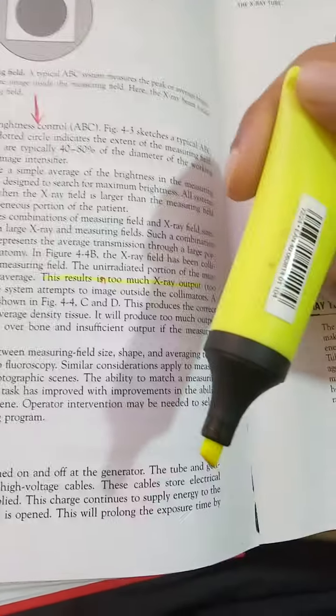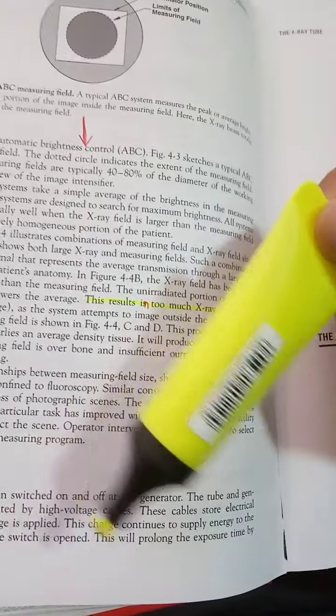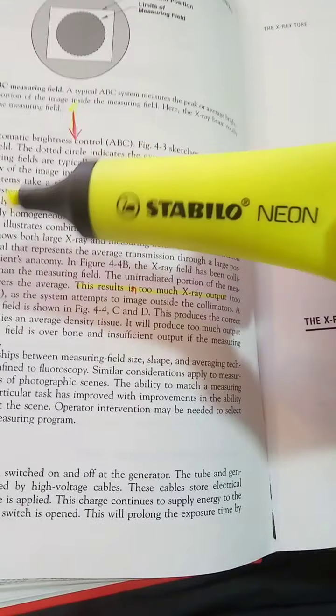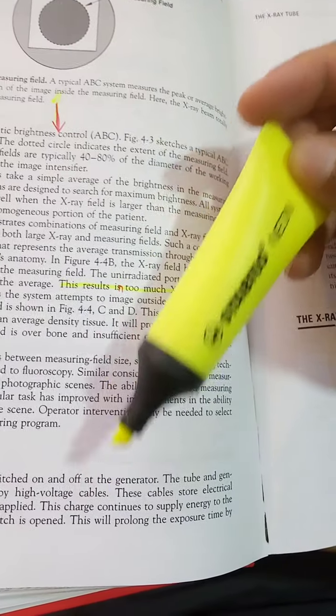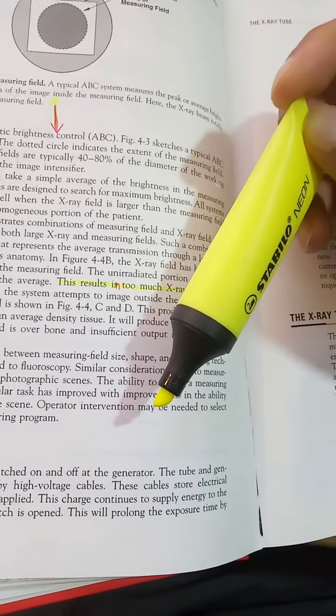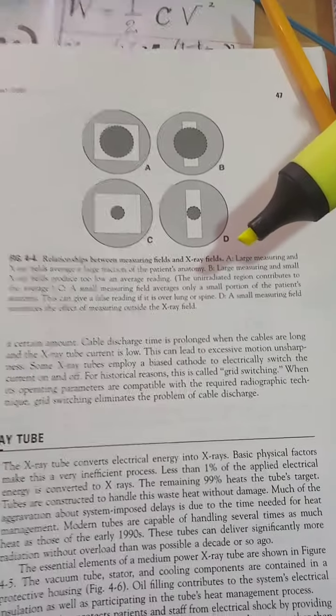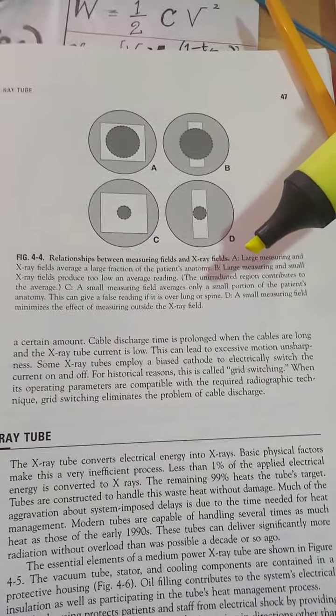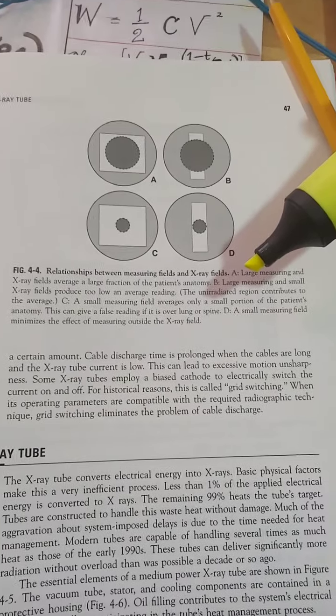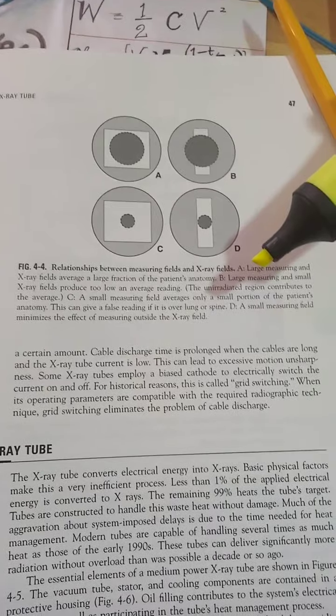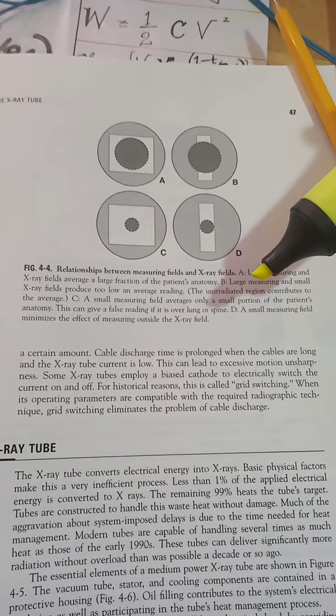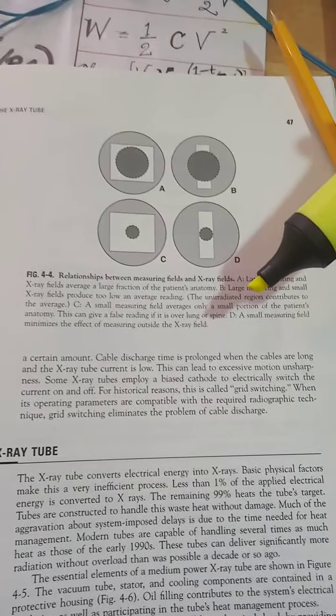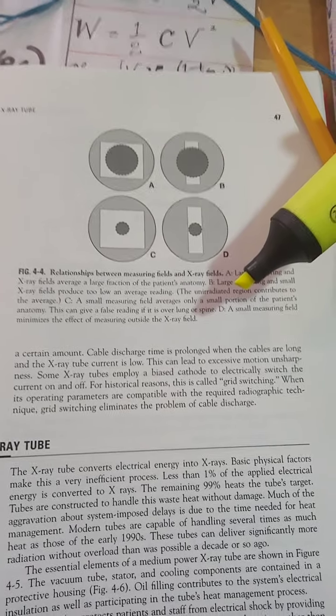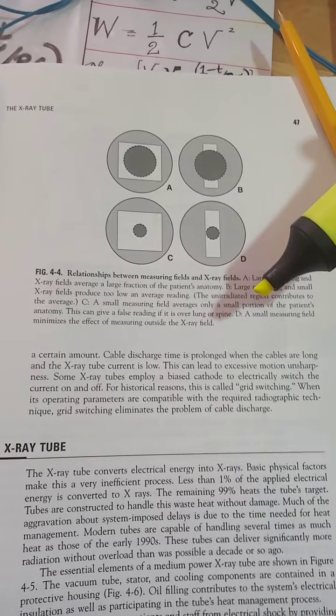The system is often switched on and off at a generator level, and the tube and the generator are connected by high voltage cables. These cables store electrical charge. When the voltage is applied, the charge continues to supply energy to the X-ray tube after the switch is opened, and this will prolong the exposure time by a certain amount. The cable discharge time is prolonged when the cables are long and the X-ray tube current is low. This leads to excessive motion unsharpness, lower resolution. Some X-ray tubes employ a biased cathode to electrically switch the current on and off. For historical reasons, this is called grid switching. When its operating parameters are compatible with the required radiographic technique, grid switching eliminates the problem of cable discharge.